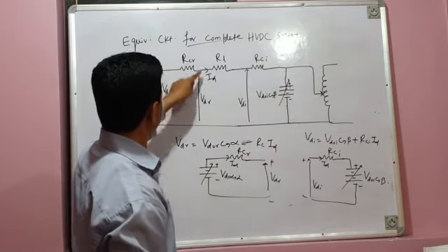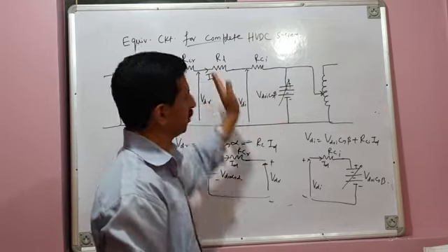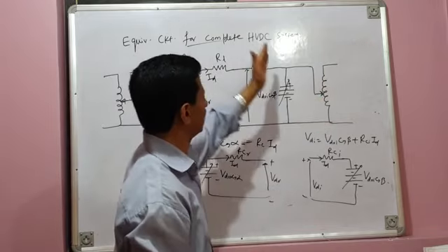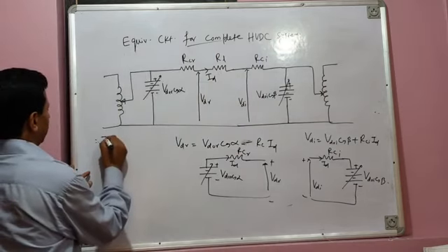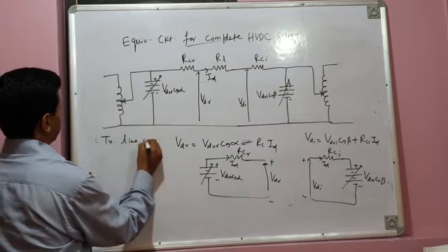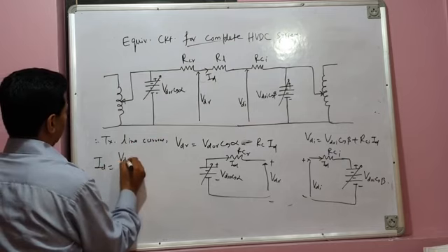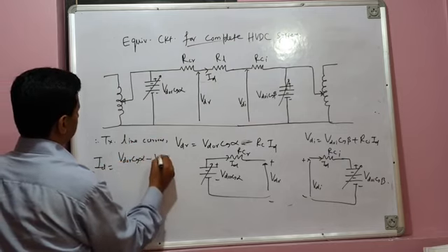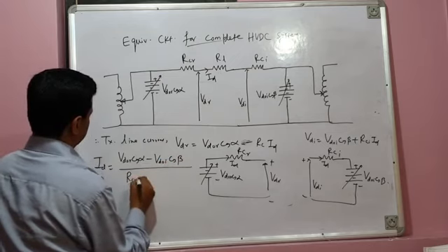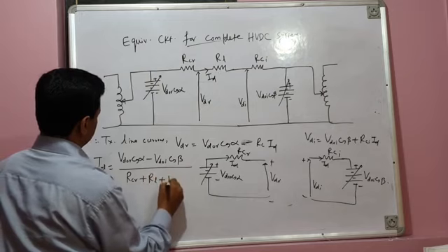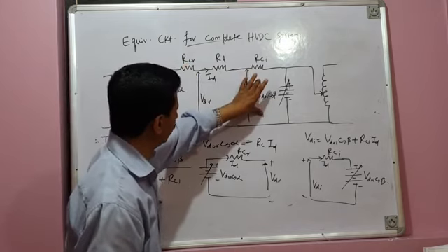So this is the electrical equivalent circuit for converter operating in the rectification mode. This is the electrical equivalent circuit for converter operating in the inversion mode. And this is converting station, this is inverting station, and this is the transmission line resistance. Therefore, transmission line current is given by ID is equal to VDOR cos alpha minus VDOI cos beta by RCR plus RL plus RCI. What is this current? It is this voltage minus this voltage divided.